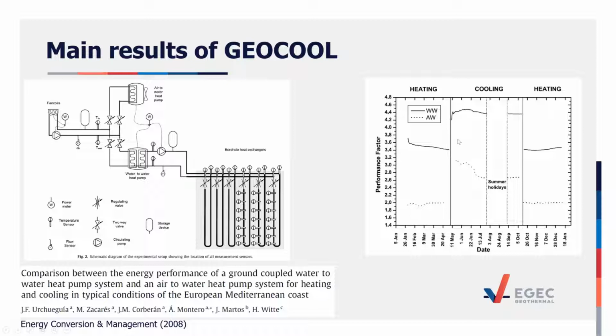Even in cooling, the difference between the aerothermal and geothermal parts is even larger, more than 60% improved performance compared with aerothermal. And I must insist, this air-to-water heat pump was a modern state-of-the-art heat pump. So the geothermal source really gives us the possibility of reaching much higher efficiency.